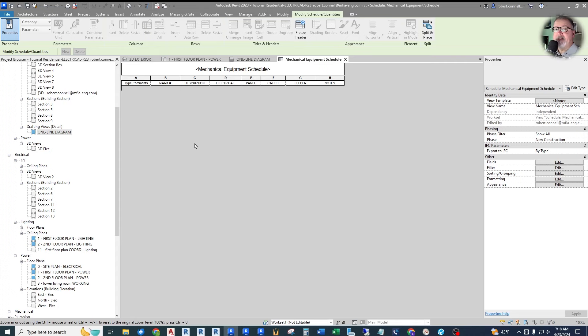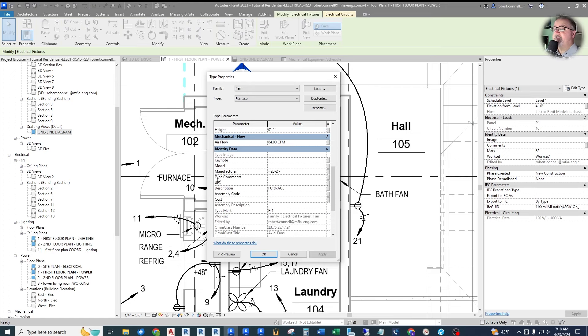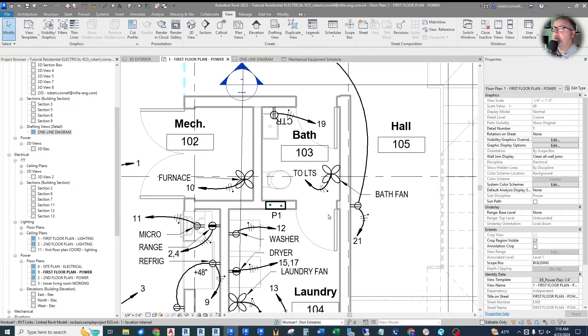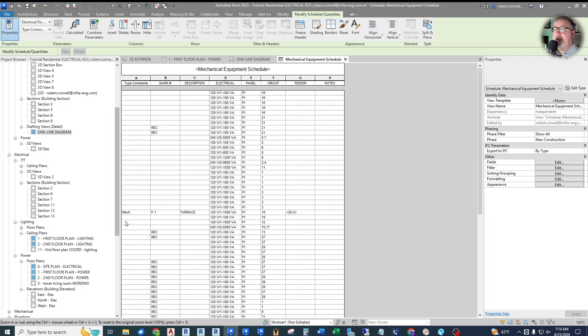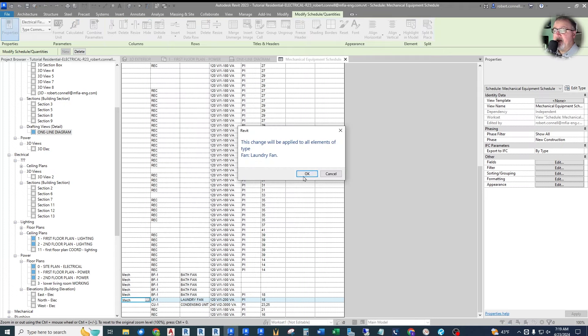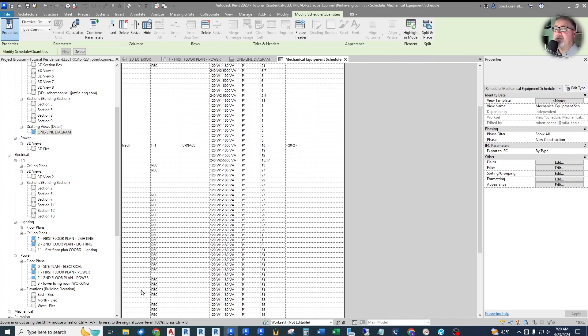For each piece of equipment, go into Edit Type and in the Type Comments field put 'MECH.' Apply that and go back to your schedule — now it shows up. We need to do that for each piece of equipment. We can turn off the filter temporarily, and then in the schedule itself we can type 'MECH' right in the Type Comments column — once you start typing, there's a dropdown since it's a type parameter, so it updates all instances. We do this for the bath fan, laundry fan, and condensing unit.